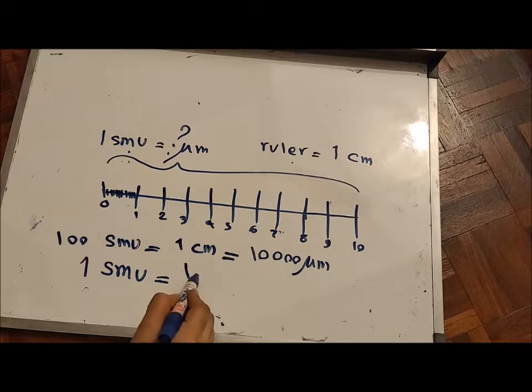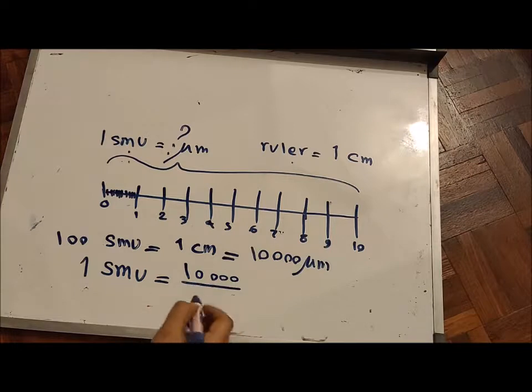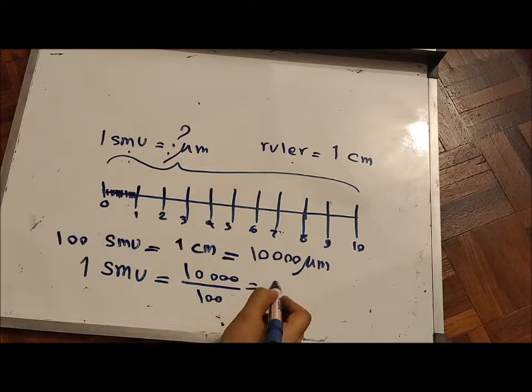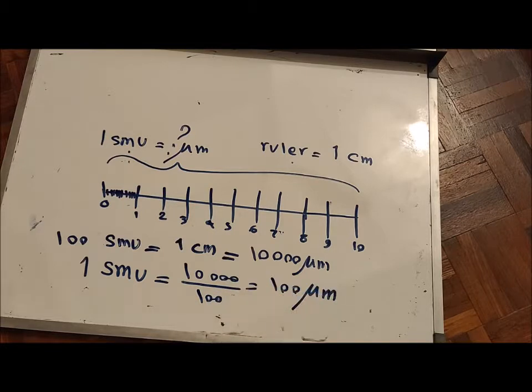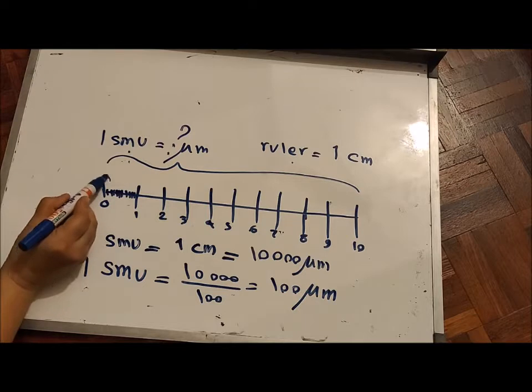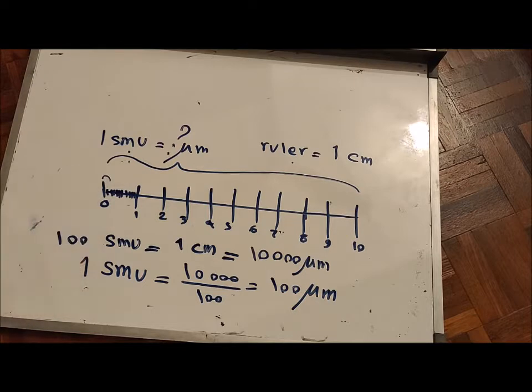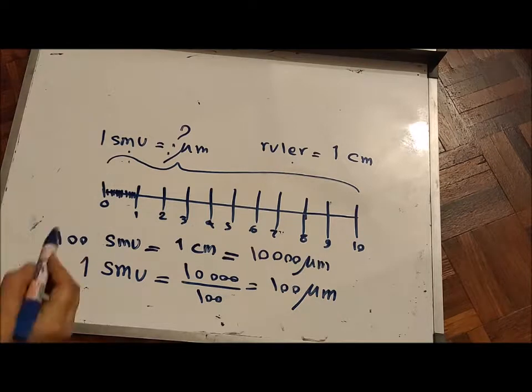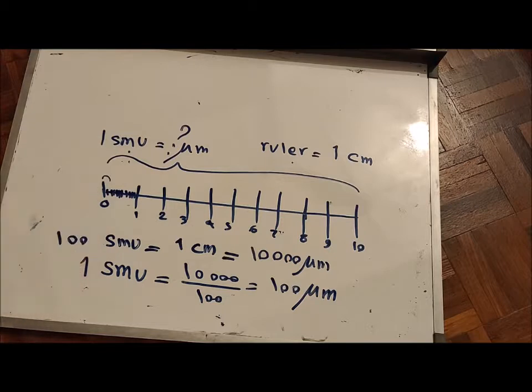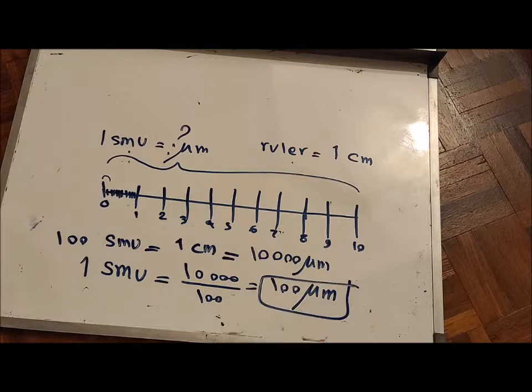One centimeter equals 10,000 micrometers. So one stage micrometer unit equals 10,000 divided by 100, which equals 100 micrometers. We have now found that each one stage micrometer unit equals 100 micrometers.